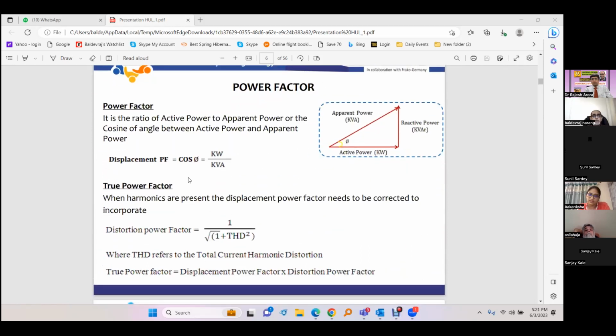So this is a displacement power factor. We have later slides on harmonics where the displacement power factor is the basic power factor. And there is a true power factor which is inclusive of the harmonic impact on the system. That is called the distortion power factor, which depends on the THD value. This is multiplied by the displacement power factor and we get the true power factor. In fact, the harmonics also have their own reactive power requirement. They are also like the normal 50 hertz supply, running into the system, consuming reactive power, and there are some losses as well. We could call that active power also required by them. So this is affecting the overall reactive power requirement too.